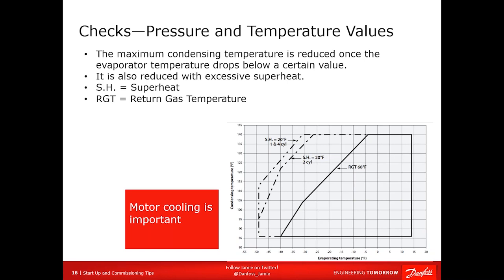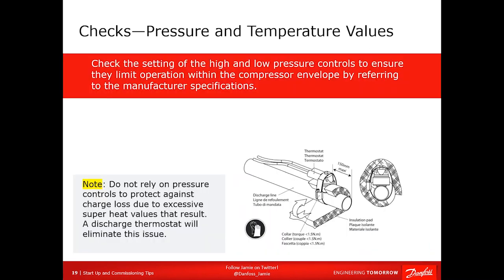If you have any questions on this, call out the manufacturer's application team. They'll basically give you a recommendation. Now, after we talked about all this, and something bad does happen, how do you protect the compressor? What is your last line of defense after everything goes out the window? Well, that would be your discharge temperature thermostat. These are starting to make more and more appearances. They're in heat pumps, low temp refrigeration systems. They're all over the place.